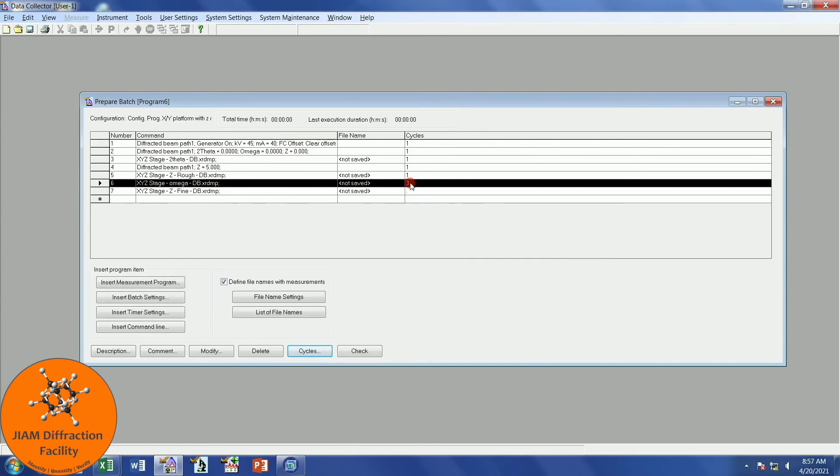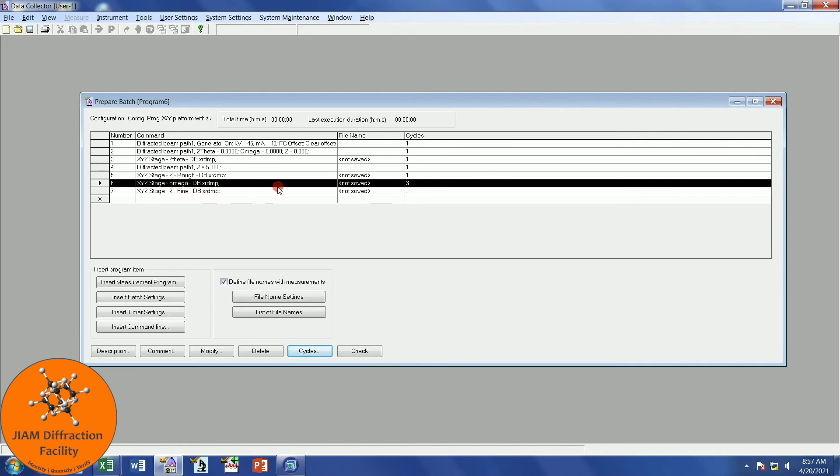We see here that we have cycles of three, and this is a period to indicate that it goes along with this three. What happens is that it will perform the rough Z alignment, then it will come down here to perform Omega, it will then perform Z-fine, it will go back to Omega, then go to Z-fine, and it will cycle Omega and Z-fine a total of three times. From my experience, that is enough iterations in order to have the Omega and Z values stabilize, but again, every situation can be different, so you might just want to watch your alignment and make sure that your values have stabilized. If not, you could just change this value to a larger number.